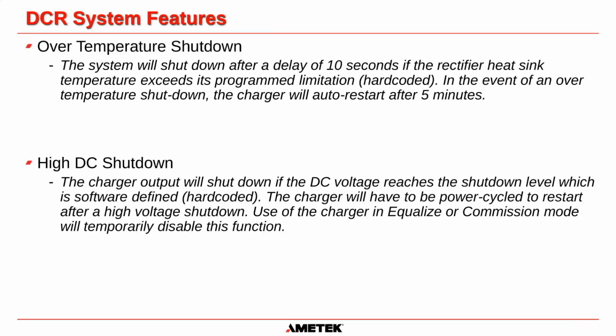Use of the charger in equalize or commission mode will temporarily disable this function. So the equalize voltage or commission mode voltage are going to be higher. It could be higher than the high DC shutdown voltage.